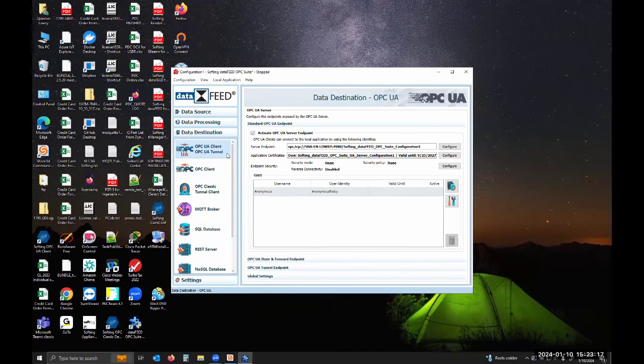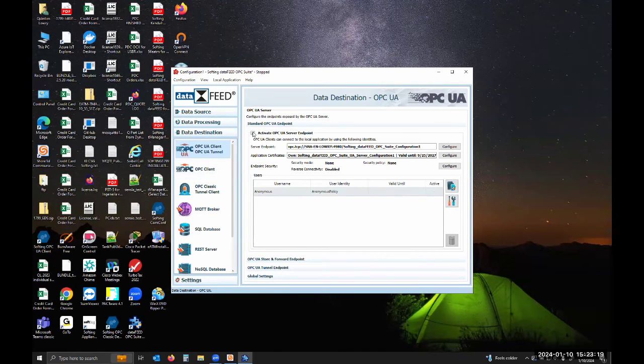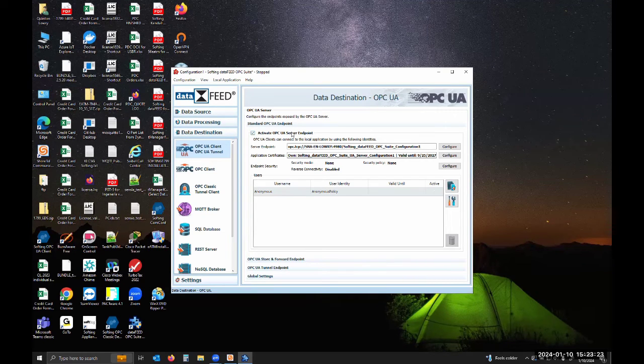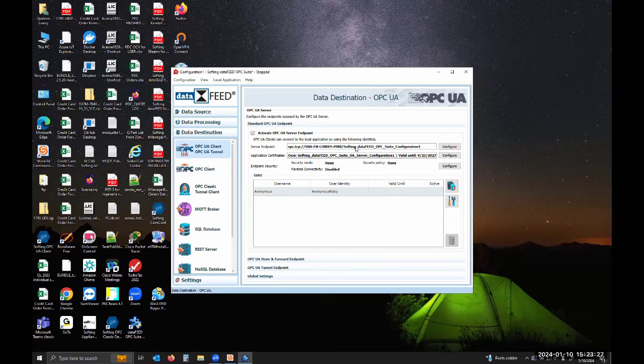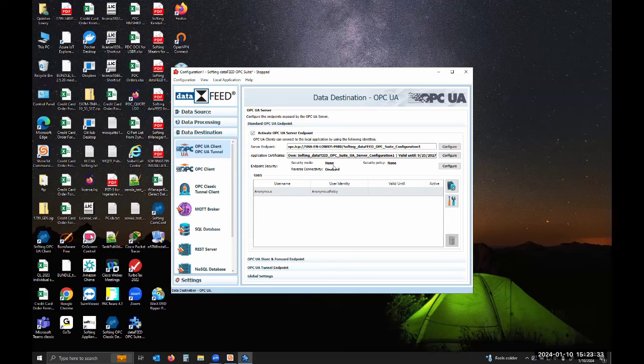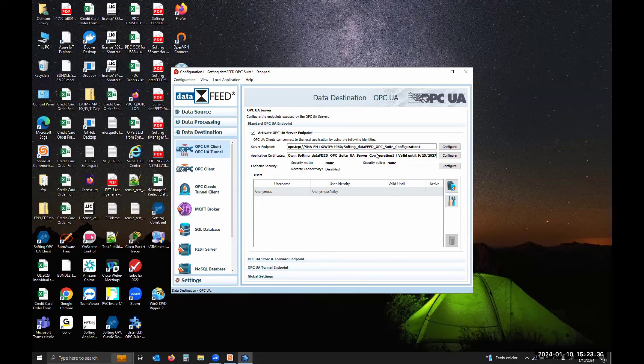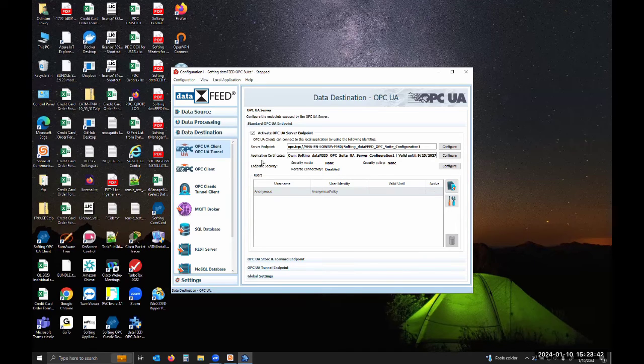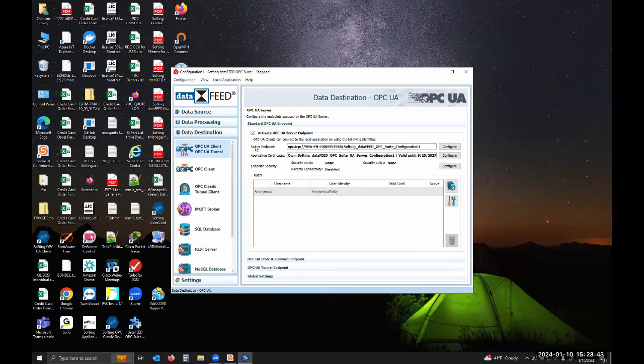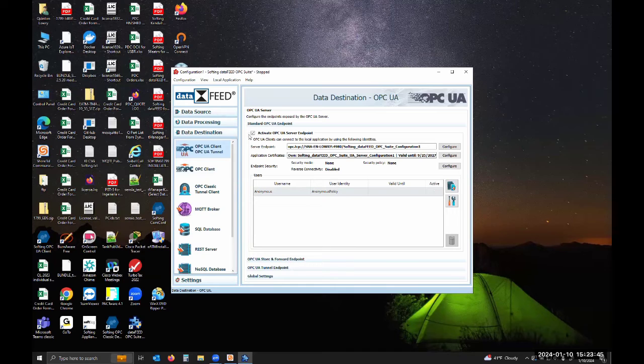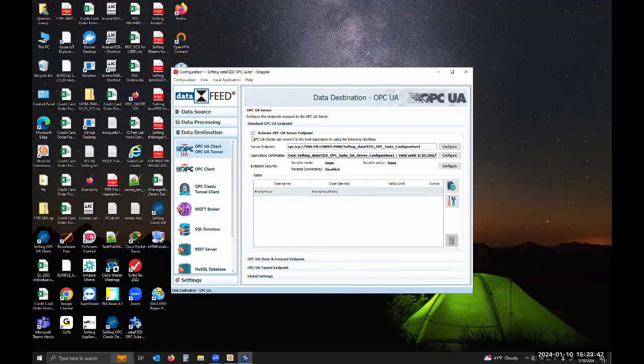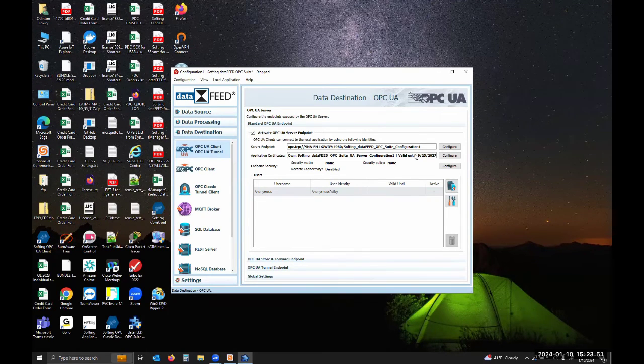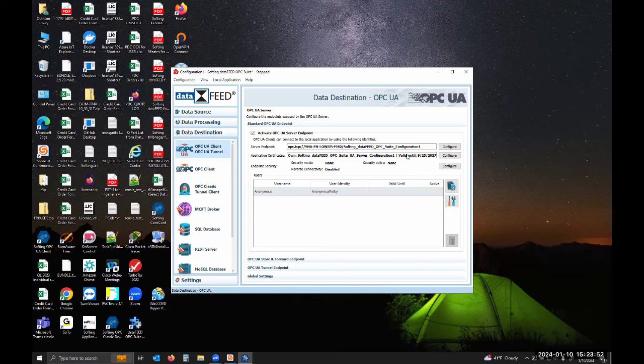If I click on data destination and scroll up to OPC UA client, you need to make sure this checkmark is there. This is the endpoint, your OPC UA endpoint that we're going to input into the client to connect to this server. You can configure different types of security and encryption as well. I'm going to leave it blank to keep it as simple as possible. I don't really have to do anything else unless I wanted to modify the security settings or the authentication.